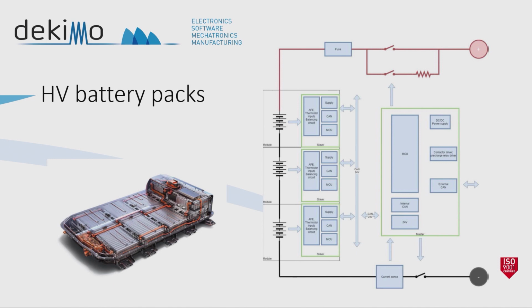If you turn the battery on and charge external equipment that has coils or capacitors, you'll get an extremely large current going out of this battery pack, which is not allowed. That's why you have two contactors: one with a resistor and one without. First you connect the contactor with the resistor to charge the equipment, then you bypass the resistor so you don't lose energy. That's how a high voltage battery pack basically works.